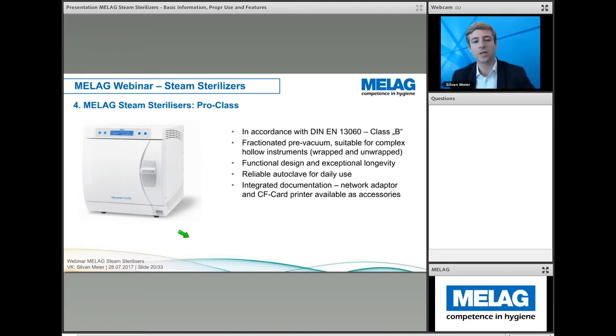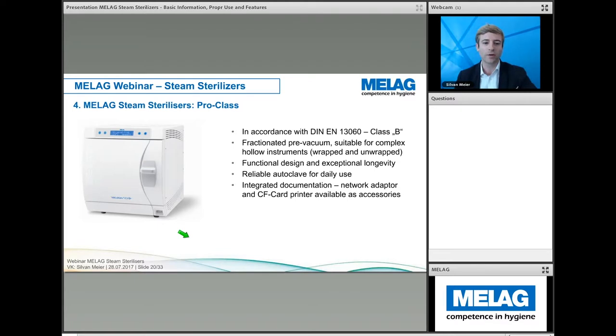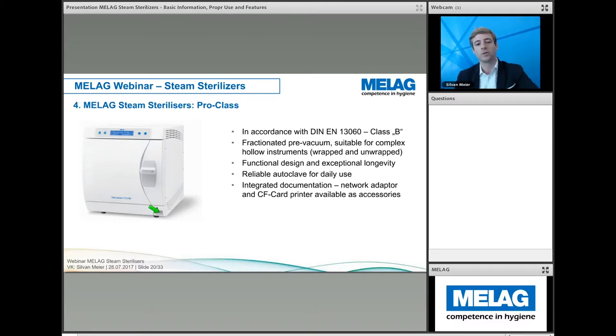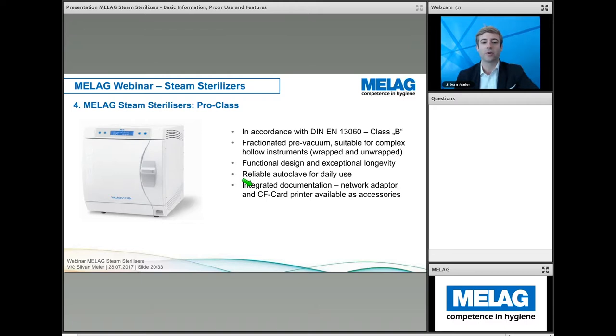Moving into Class B, the ProClass Vacuklav autoclaves comply with European standards and work with fractionated pre-vacuum, suitable for all kinds of instruments — especially complex hollow instruments, both wrapped and unwrapped. They feature a functional design and are one of our most popular autoclaves, widely sold around the world, reliable for daily use and even for heavy users. Documentation works via the network adapter and CF card printer accessories.